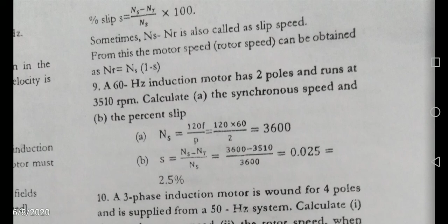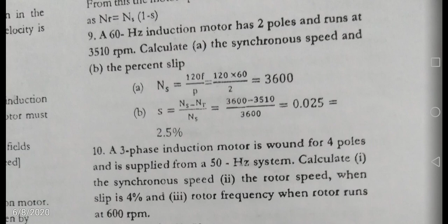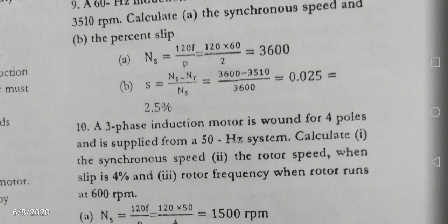Ninth question: a 60 hertz induction motor has 2 poles and runs at 3510 rpm. Calculate the synchronous speed and the percentage slip. Ns equals 120f by P, 120 into 60 by 2, that equals 3600 rpm. S equals (Ns minus Nr) by Ns. Ns is 3600 rpm and Nr is 3510, so the value is 0.025, that is 2.5% slip.